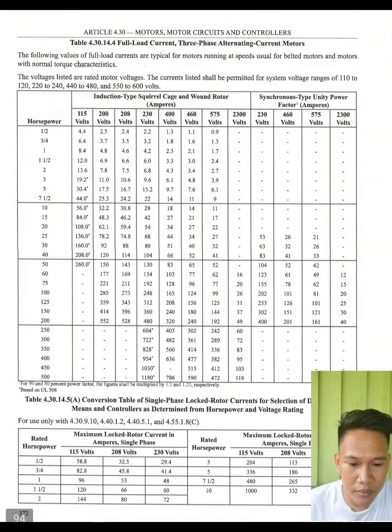So next is table 4.30.14.4, full load current, three-phase alternating current motors. The following values of full load current are typical for motors running at speed usual for belted motors and motors with normal torque characteristics. The voltages listed are rated motor voltages. The current listed shall be permitted for system voltage ranges of 110 to 120, 220 to 240, 440 to 480, and 550 to 600 volts.